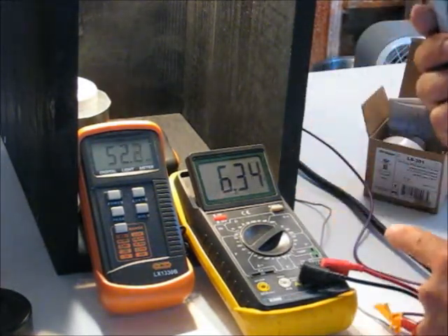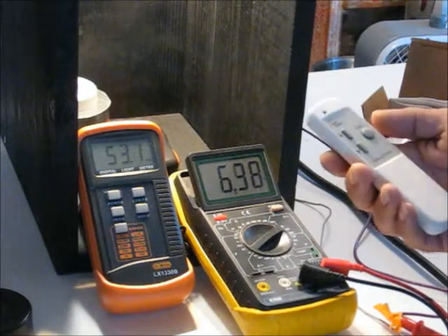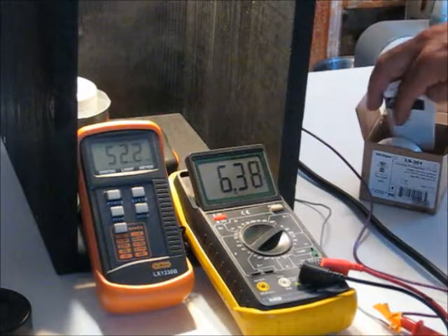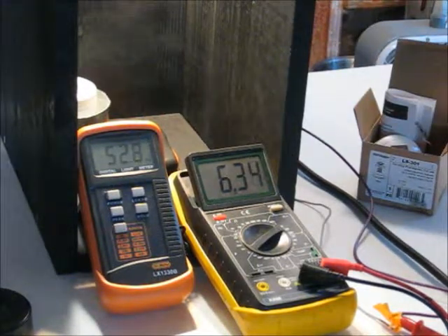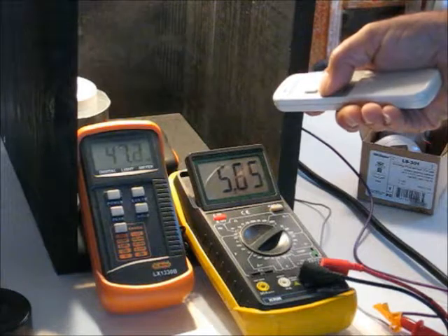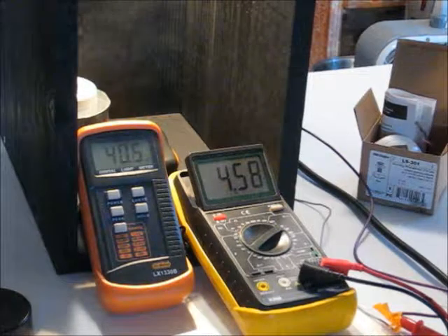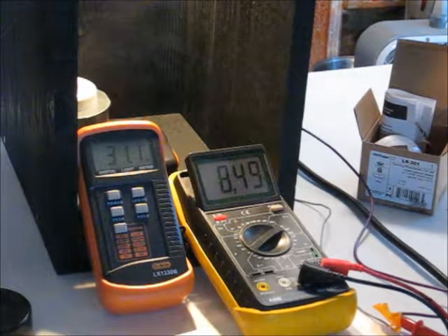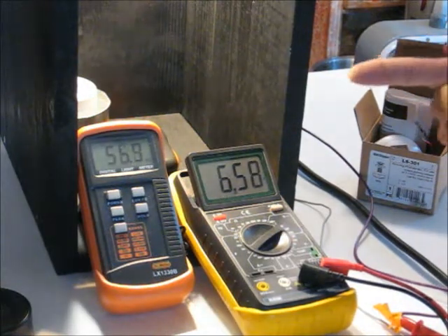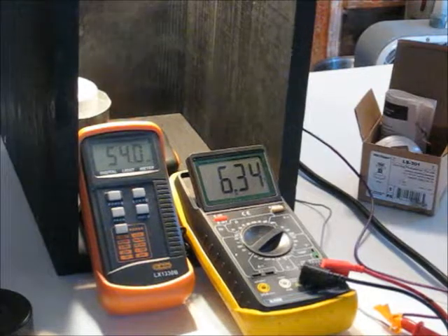And this is not the only device like this that is currently in use in the state of California, I'm pretty sure. Also, it's no big deal, because you can put the sensor on the area control, and let's say I dim it all down or up, either way, and I cut the power to the daylighting system lights, and it cuts the power to the sensor. When I re-energize the sensor, and you can take my word on it, that's going to go back to 52 foot candles, where it is designed to be.